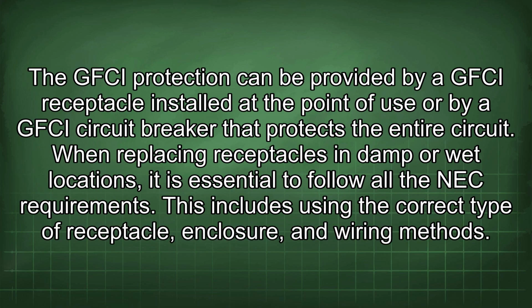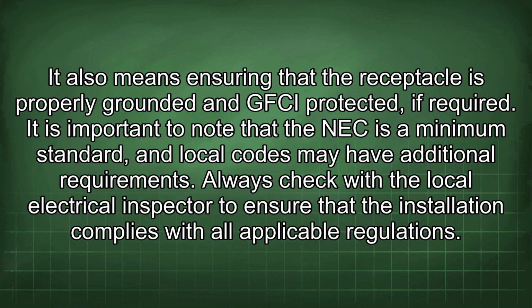The GFCI protection can be provided by a GFCI receptacle installed at the point of use or by a GFCI circuit breaker that protects the entire circuit. When replacing receptacles in damp or wet locations, it is essential to follow all the NEC requirements. This includes using the correct type of receptacle, enclosure, and wiring methods. It also means ensuring that the receptacle is properly grounded and GFCI protected if required.